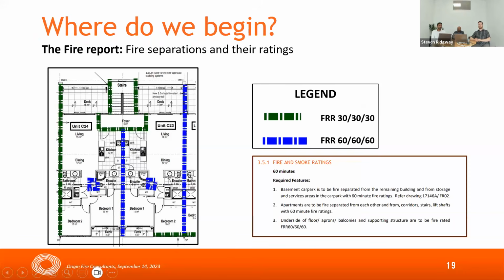Next one. So where do we begin? As passive fire engineers, we definitely begin with the fire report. In a typical fire report, you have the fire separation drawings and the fire rating. I've just added a clip here from one of our fire reports. Here there are two apartments, one on each side, and there's a fire protected stairwell. Almost every fire report will have this drawing showing the fire separation. Here it's showing a 30-minute rating for the external wall, and then you have a 60-minute rating between two apartments. What that means is you need a fire resistance rating of 60/60/60 between these two apartments.